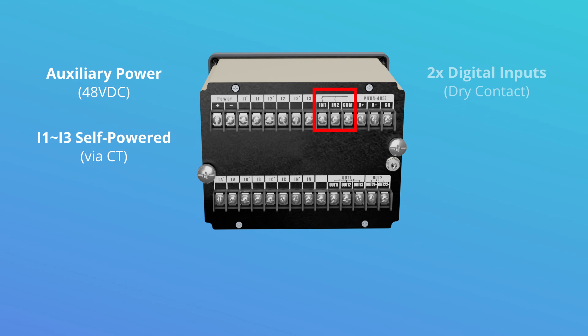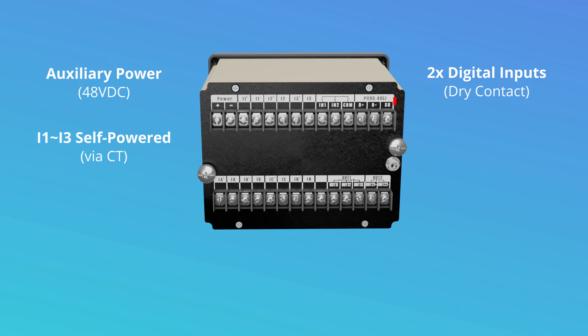There are two digital input terminals. They are dry contact inputs that can be used for monitoring the status of, for example, breaker status, external trip signals, or configured as DI protection for gas trip, temperature alarm, remote signaling inputs, etc. The serial port is for communication with your workstation via Modbus RTU for remote monitoring, settings, and control.